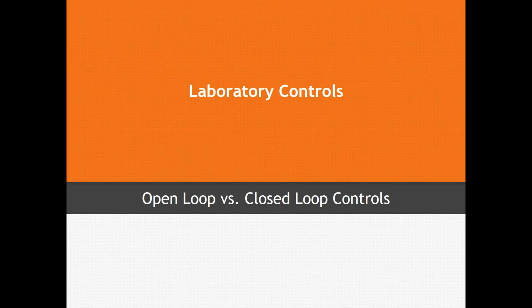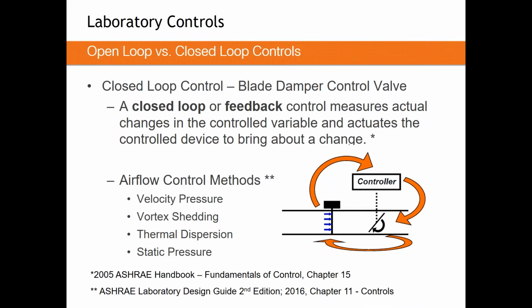So let's move on from the valves over to open loop versus closed loop devices. We grouped the valves into mechanically pressure dependent and mechanically pressure independent. And really what we were introducing is closed loop versus open loop controls. So in a high accuracy terminal in a VAV box, we're doing what's called closed loop control. Again, we measure airflow, which also happens to be our controlled variable. We measure airflow and move a damper to control that airflow. We measure and move over and over and over again. This is a closed loop style of control.